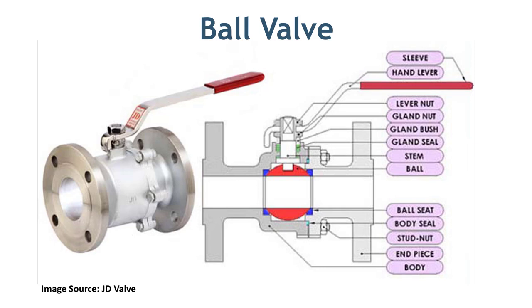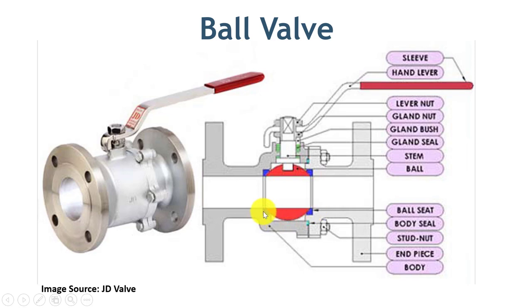On this slide, you can see the cross-section of the ball valve. This is a split body side entry valve. Here you can see that the body is smaller than the gate and globe valve. The disc is in ball shape — that is why it is called a ball valve. There are two seats, one on the upstream and the other on the downstream. Unlike the gate and globe valve, the seat will always remain in contact with the ball-type disc. The cavity inside the ball-type disc allows the fluid to pass through the valve.